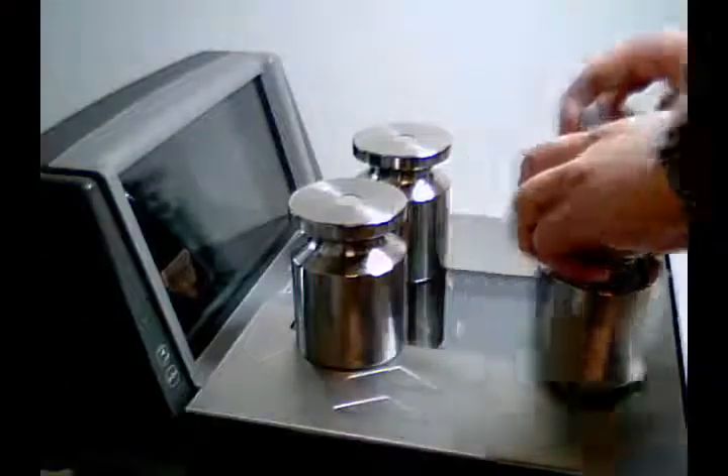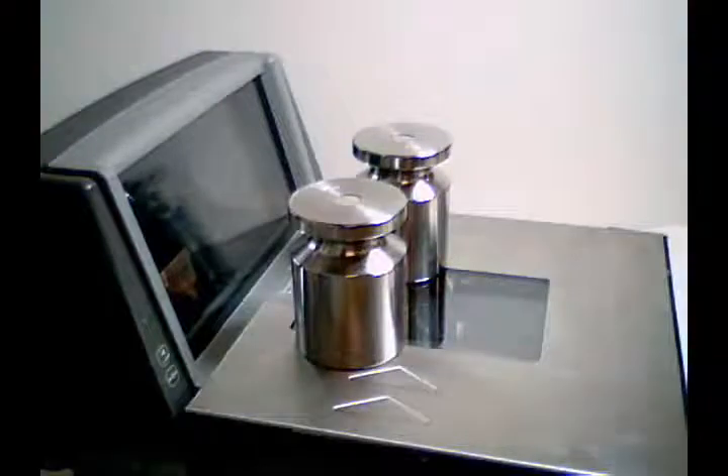Remove the weight and leave the platter empty. Finally, press the zero button again and the scale will reset. Now you can test your calibration.